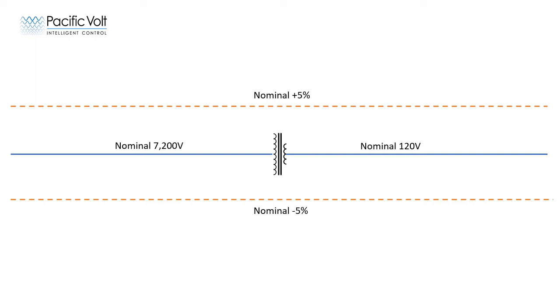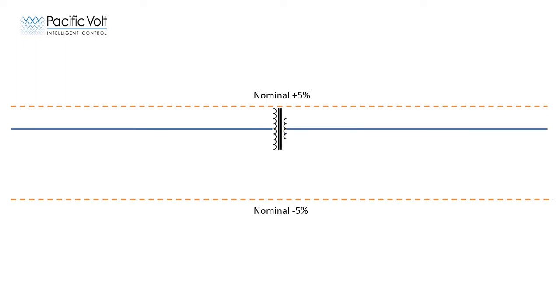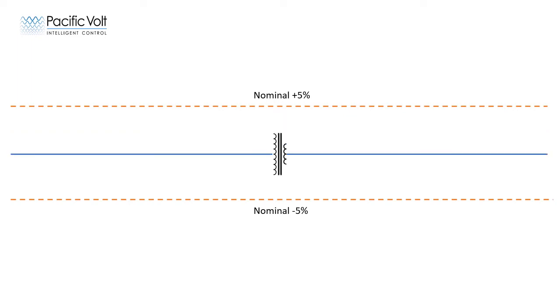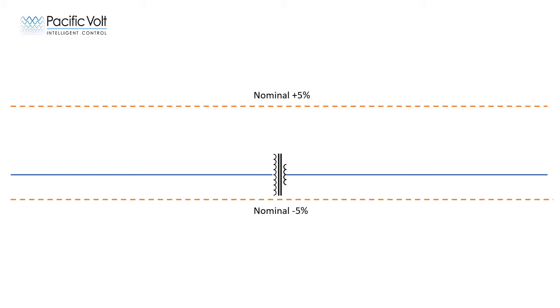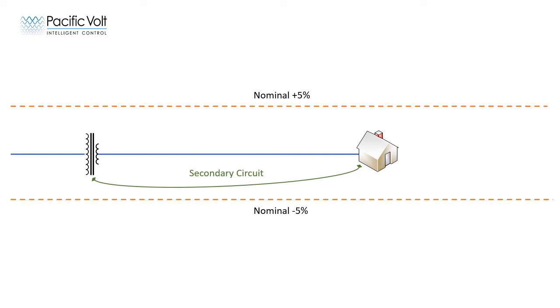In order to comply with the voltage delivery standards, the voltage on a medium voltage feeder should stay within plus or minus 5% of 7.2 kV. The medium voltage input to the transformer rises and falls, depending on how much power is consumed on the feeder. This is especially true near the end of the feeder. The secondary circuit is defined as the low voltage side of the distribution transformer and the wires connecting it to the building. Historically, the secondary circuit voltage has received little attention. It was assumed that if the medium voltage feeder was regulated properly, the secondary would also be okay.